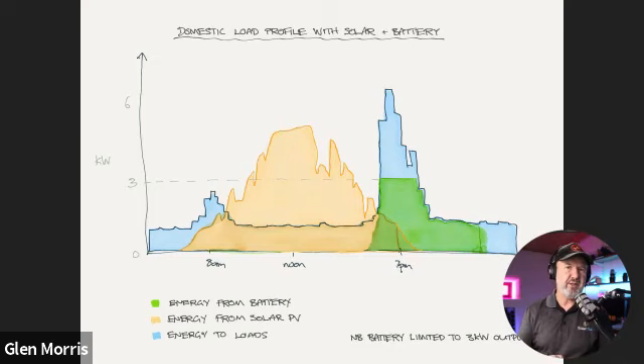So you're not having to go through a low frequency transformer to step the voltage up from 48 volts to 400 volts internally, and therefore the high voltage battery is connecting directly onto the DC bus of the inverter at high efficiency, and it also means the cable sizes are very small and your losses are very small. So instead of putting in 50, 70 mil cable, you're putting in 6 mil cable. So everything's cheaper to install, more efficient, and the inverters are much, much cheaper because they don't have a large toroidal transformer inside them. They're transformer-less.